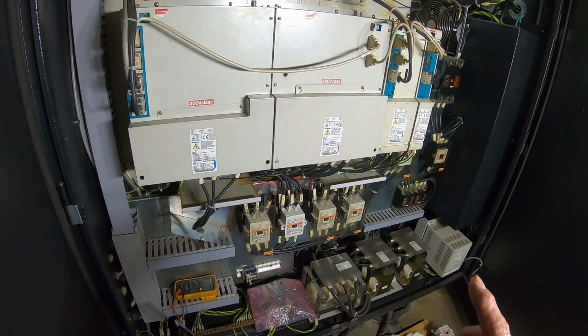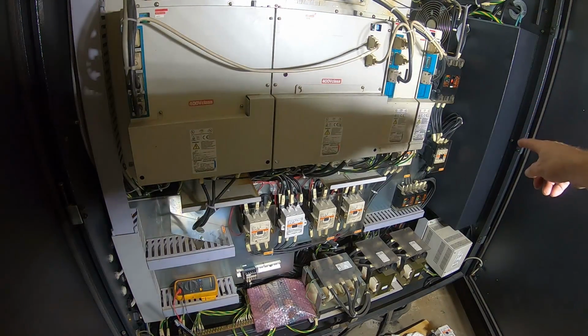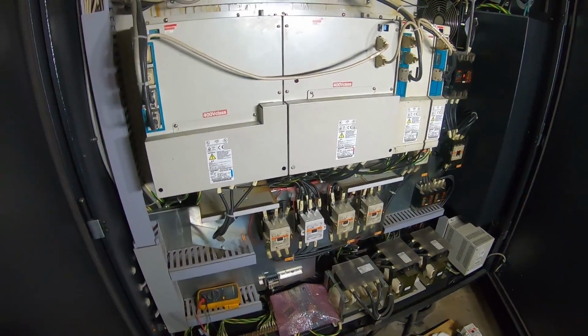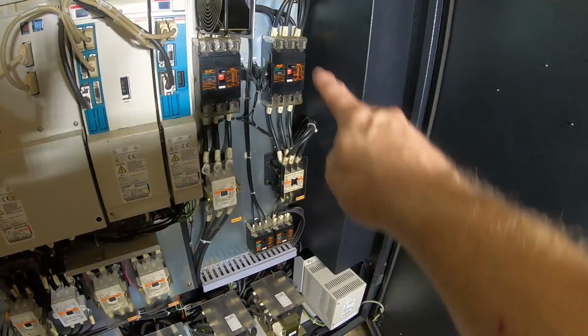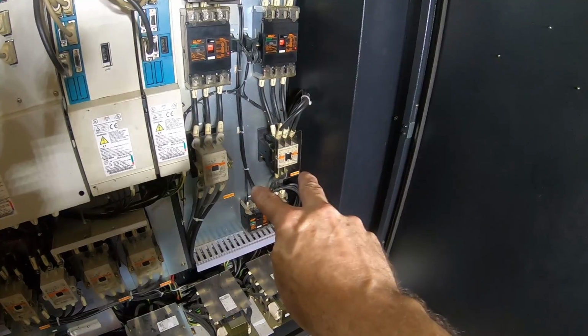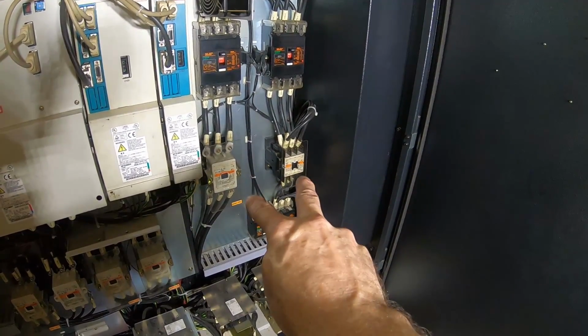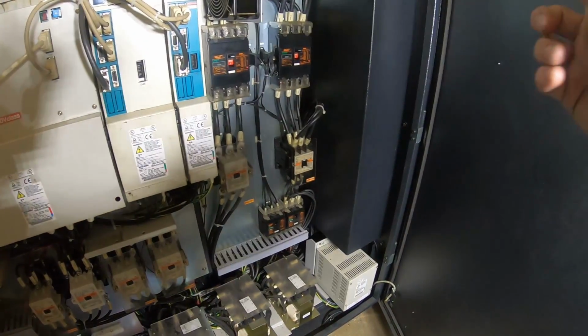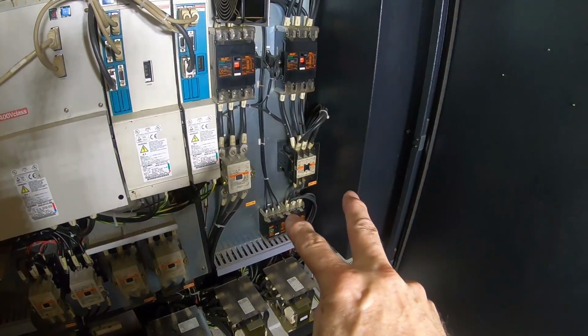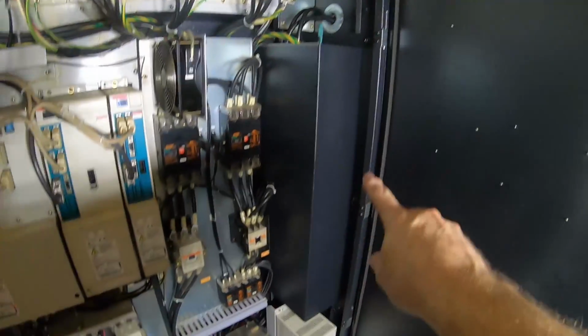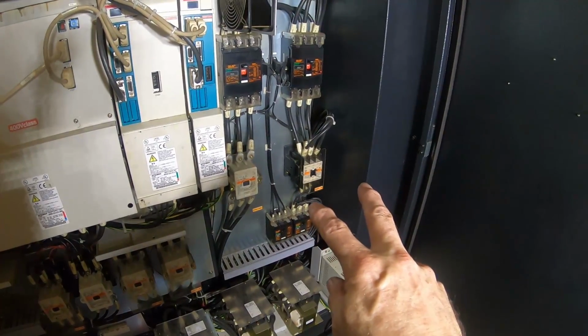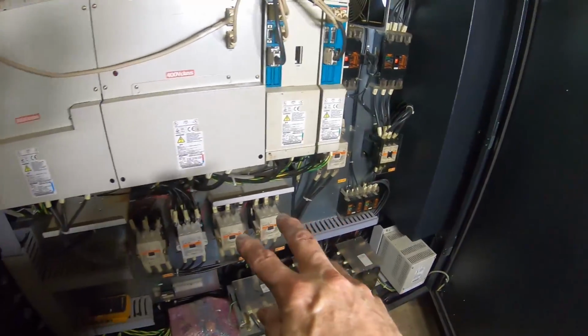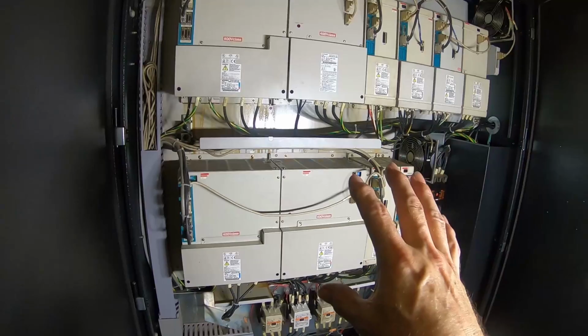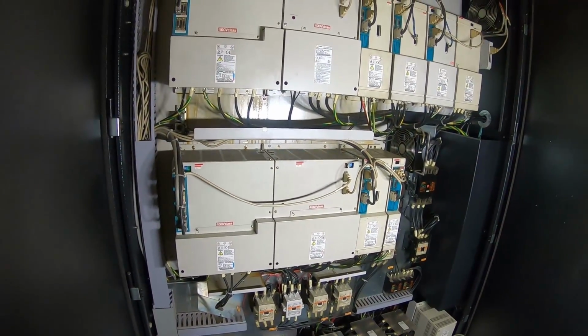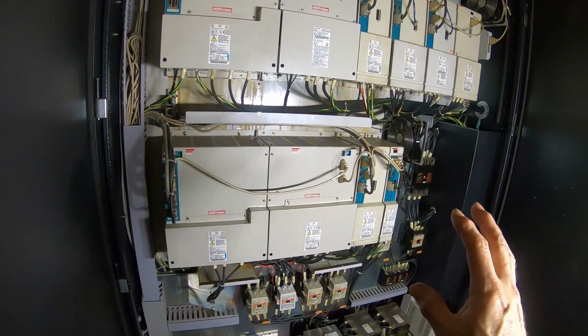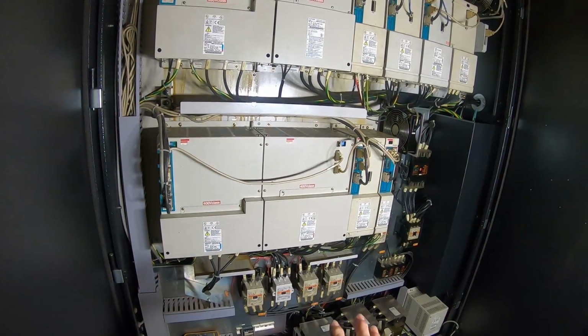I don't know why Mazak makes their machines this way, but they have these great big contactors on the main power that you can't see from this view. The main power comes in through these 2 circuit breakers, but for some reason they leave that on continuously even though the control is turned off. That main power goes down to a circuit breaker behind that panel. If you leave that on, all of this remains enabled all the way up through these relays, and the spindle drives all remain on even though the control is off, or even if emergency stop is depressed. With the main power coming in turned on, this all remains enabled.